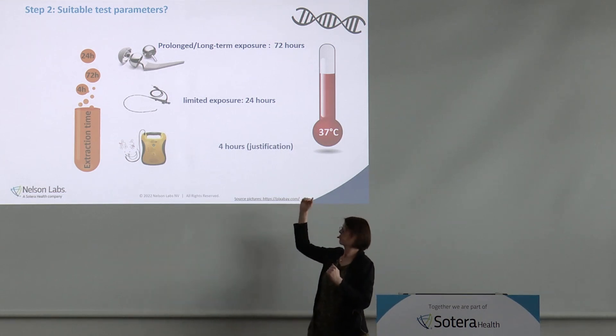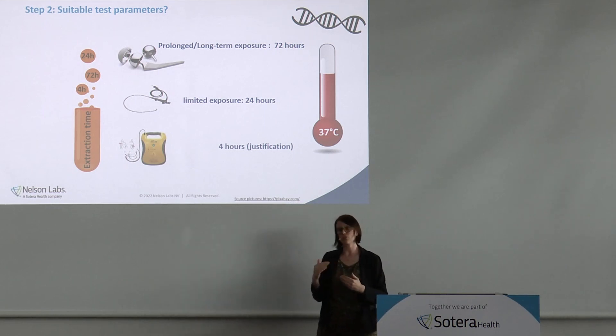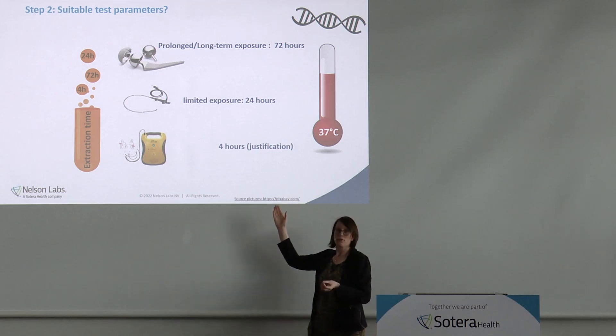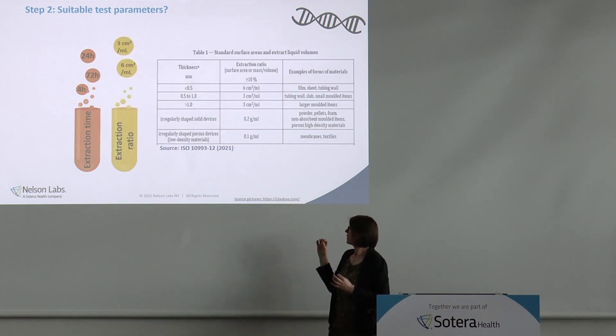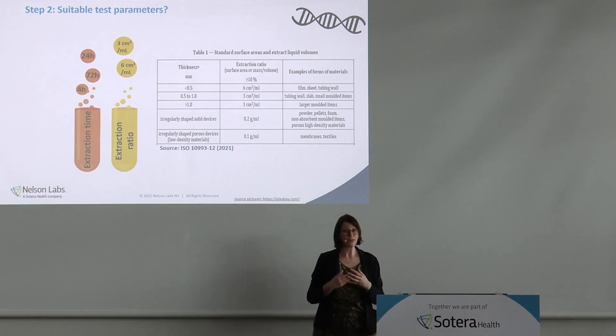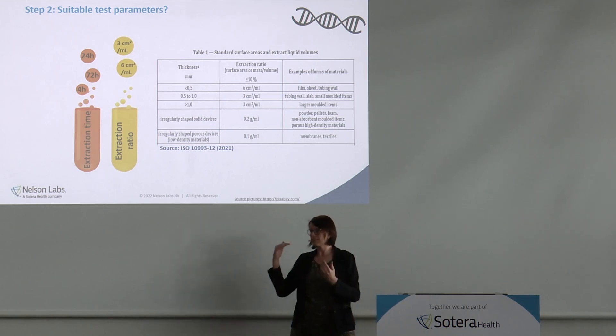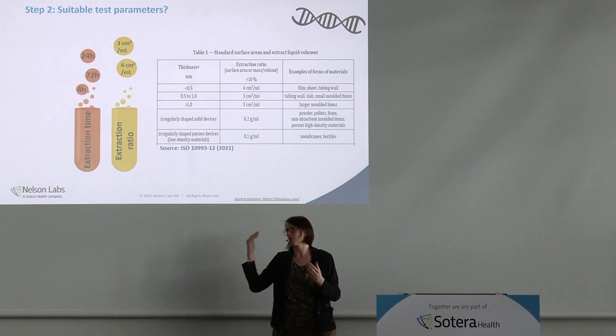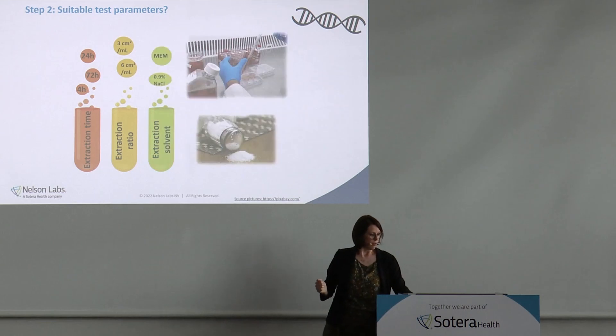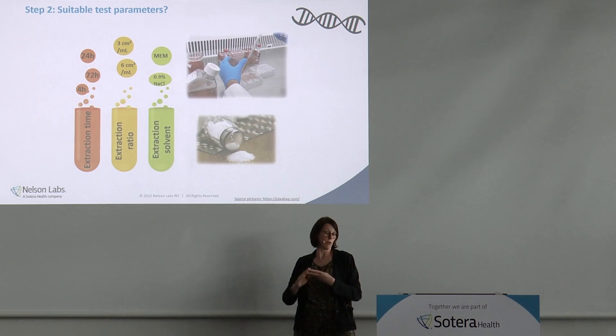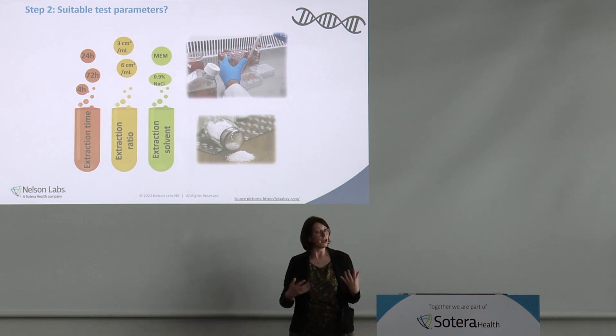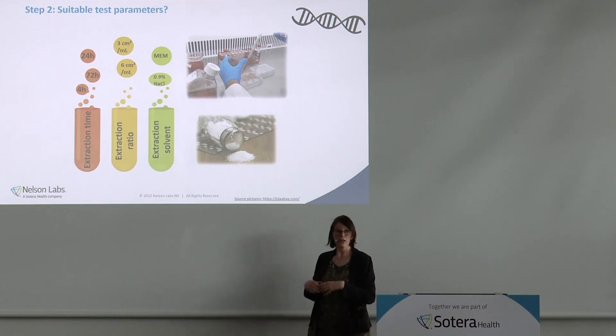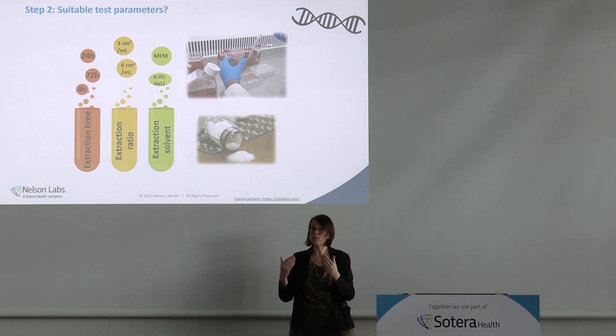If you want to go below 24 hours, you really need to justify that your device is only a few seconds in contact with the patient and 24 hours is too extreme. Other important parameters include the extraction ratio, described in ISO part 12: six square centimeters per milliliter, three square centimeters per milliliter, or a weight-per-volume ratio. You might reduce from worst case. Also look at the extraction solvent — normally MEM solution is used, which has both polar and non-polar properties and is preferred. But if your device only contacts an aqueous solution, you could choose a polar extraction solvent like 0.9% sodium chloride, with justification.